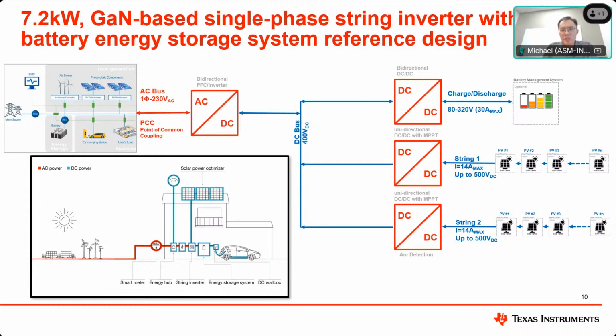We rated this design when we started for 7.2 kilowatt, and later on we realized that 8 kilowatt on the PV string input side can also be achieved with margin. The outputs of the string DC-DC boost stages are connected to the common DC bus that is rated to work at 400 volt normally. The second building block in this design is the bidirectional DC-DC that is connected to a battery pack that can range from 80 volt up to 320 volt. But 400 volt can also be possible since the DC bus voltage is nominally 400 volt, but it can be higher.